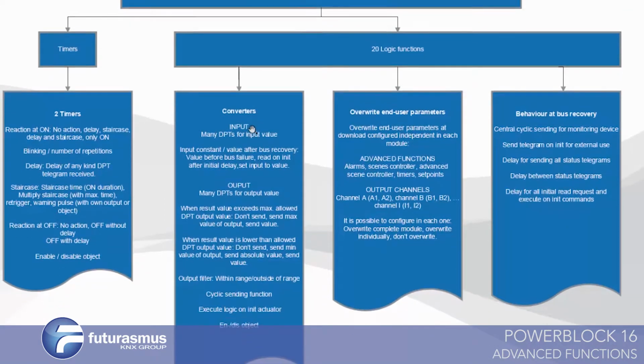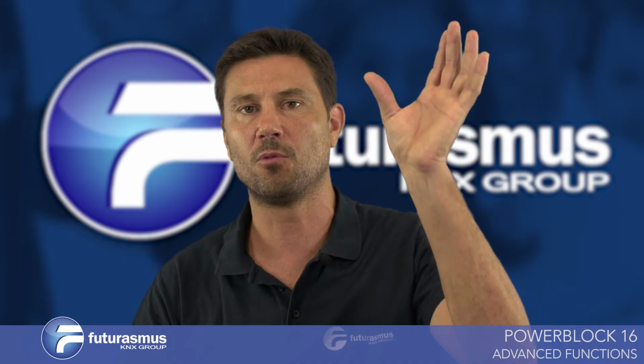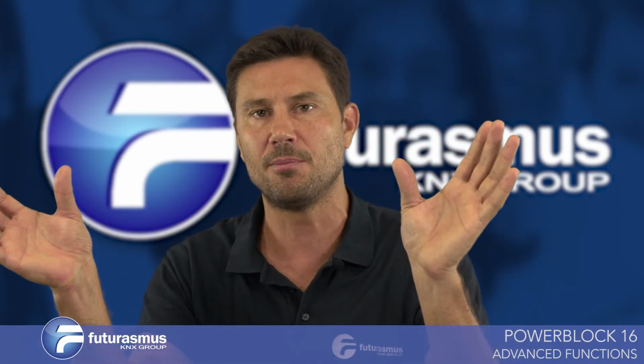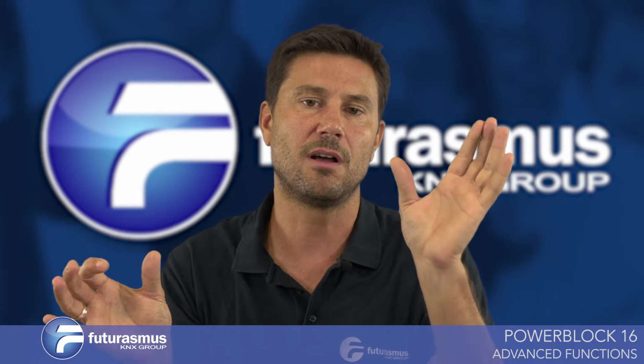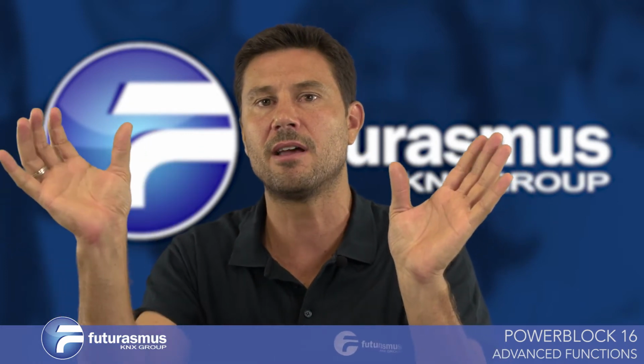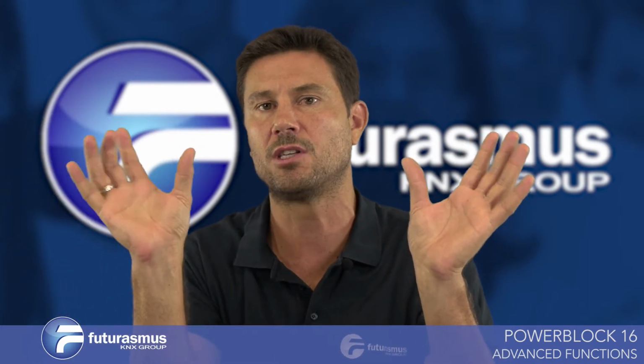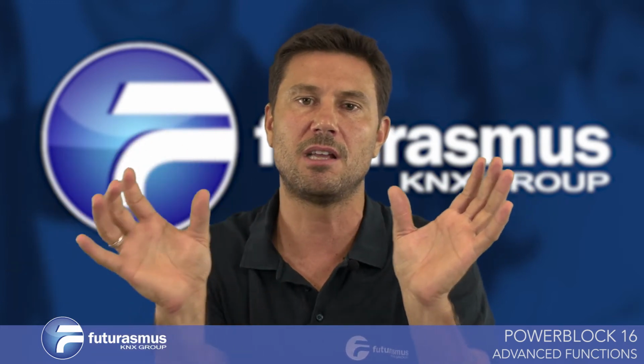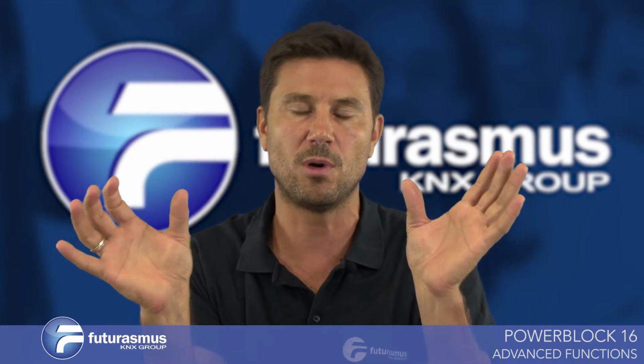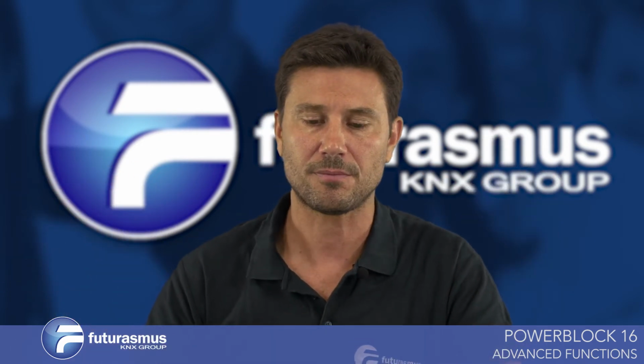Then you've got converters, which can convert the data point type from one data point type to another data point type, and you can decide what should happen if your output value is higher than the data point type allowed value, or if it's lower than the data point type value. So you can define the converters.